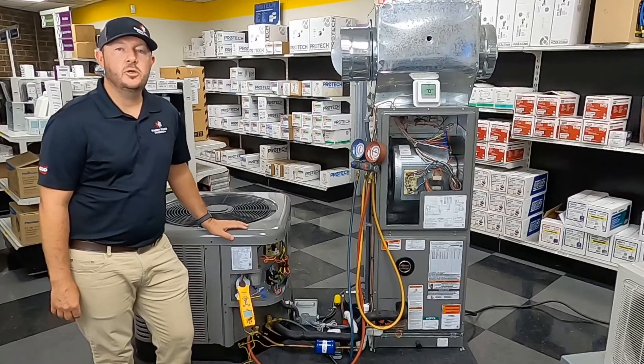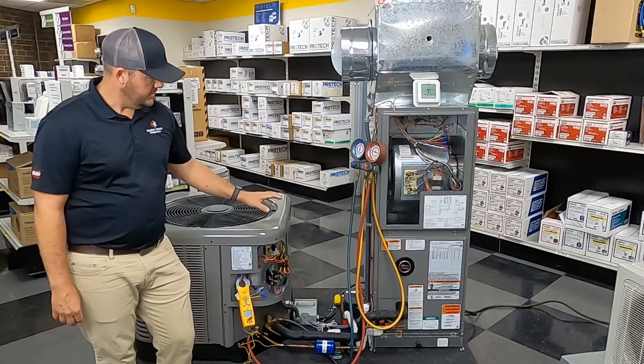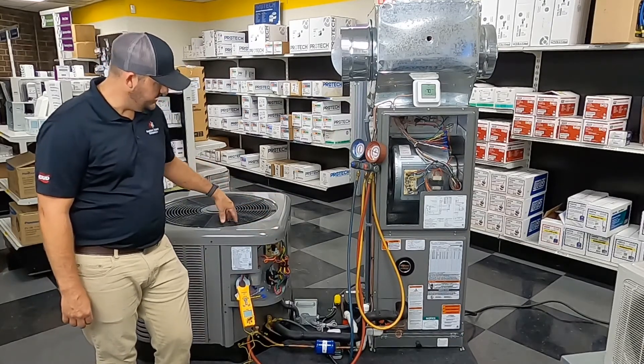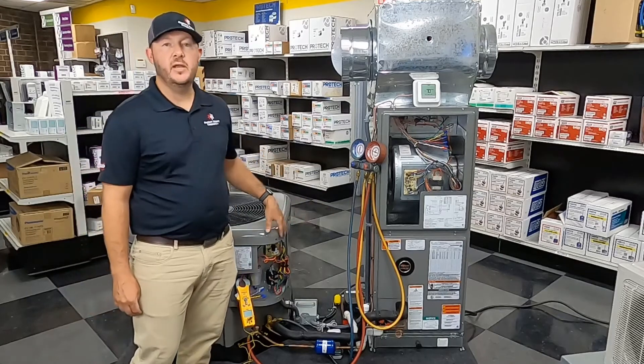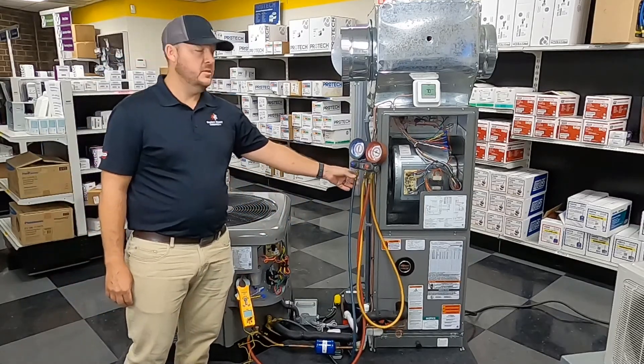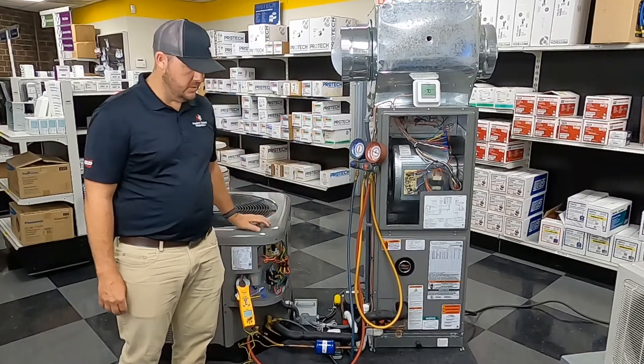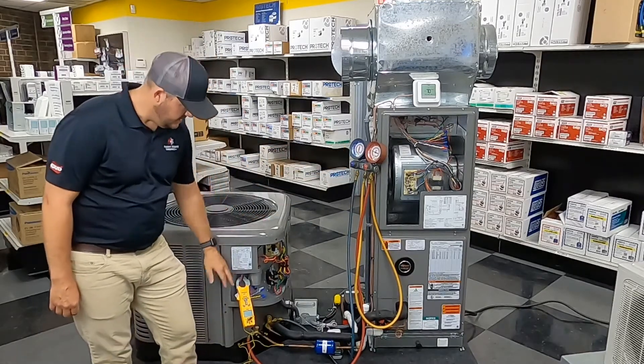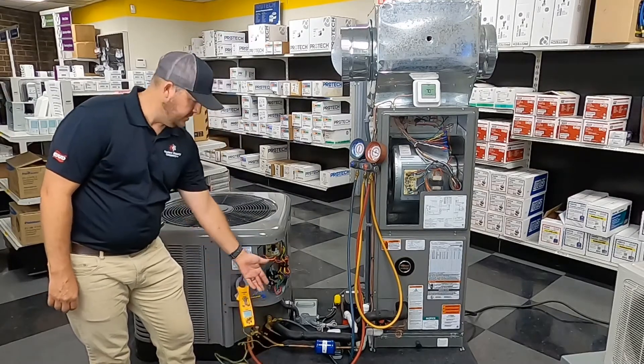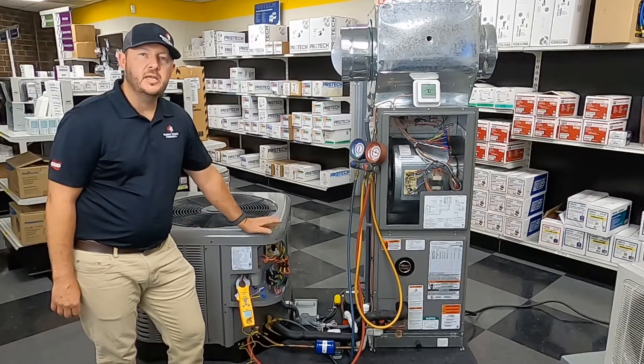Let's get started on charging up this system. We've got a two-ton 14 SEER heat pump. We've got a TXV in the outdoor and also a TXV in the air handler. I'm just going to be using analog gauges for this one — keeping it very simple, something everybody should have. I've got a Fieldpiece temperature probe; I'm just going to tape it on the line. Keeping it very simple.